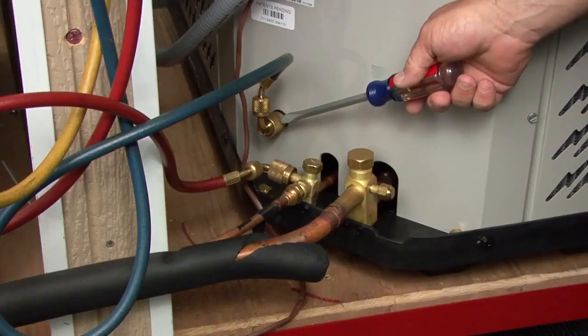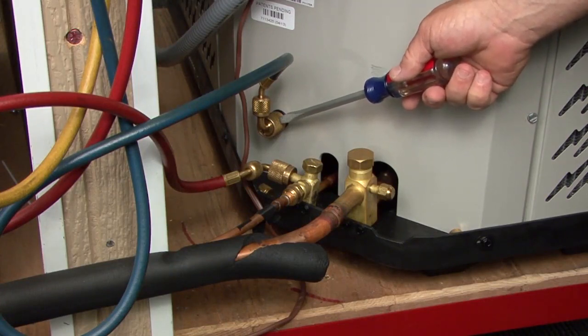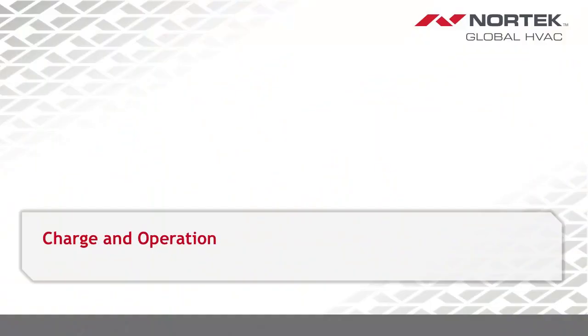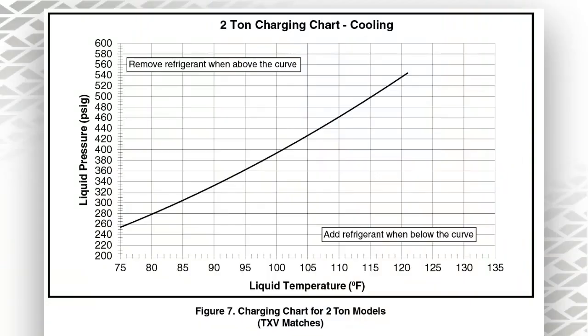Okay, so now that we know where our gauges need to be located, now what we can do is talk about verifying the operation and the charge of the unit both in heating mode and in cooling mode. When you're out there doing maintenance checks, or if you're doing a new startup, you're not always going to be able to pick the temperature outside. So checking the charge by using a charging chart is going to be best utilized for the temperature you've got outside. So we've got 3 types of charging charts that come with the equipment. If you've got an indoor TXV and you're checking in the cooling mode, you're going to use the subcooling curve chart.